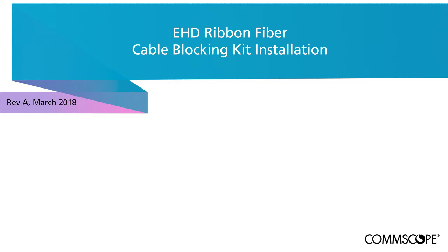This video will detail the procedure for installing the CommScope cable blocking kit required to prepare a 288 fiber ribbon cable for splicing to ribbon fiber splice cassettes in the CommScope EHD fiber chassis. The blocking kit components and the installation procedure are applicable to both standard matrix ribbon and rollable ribbon cable types.